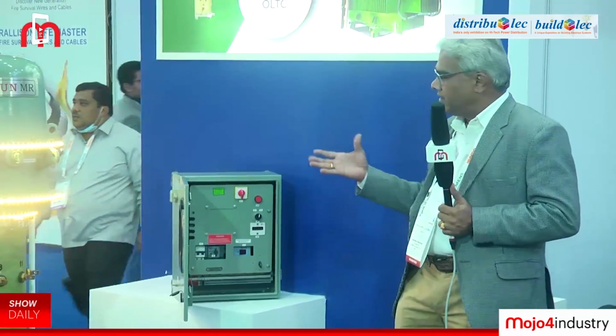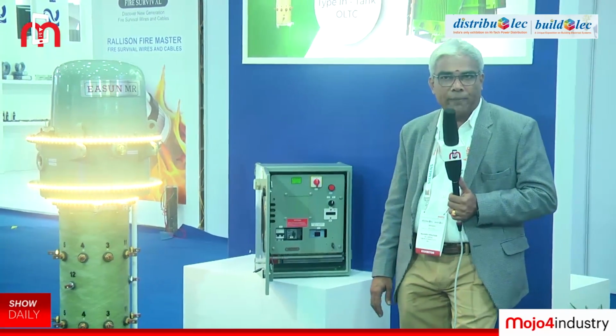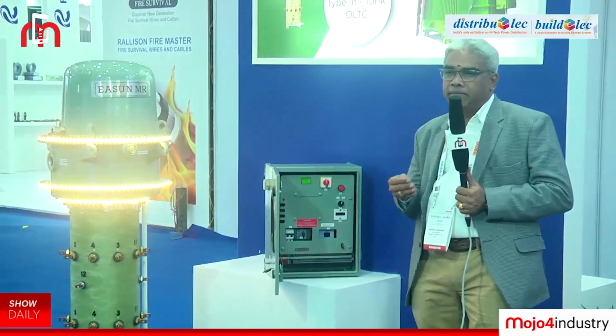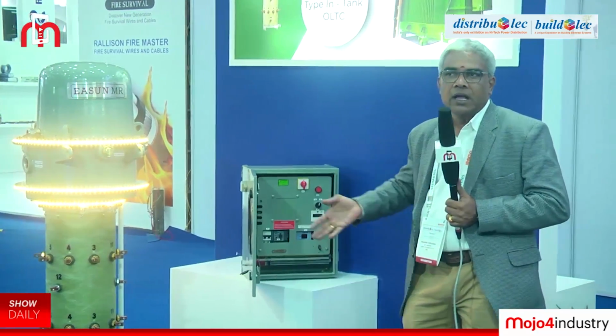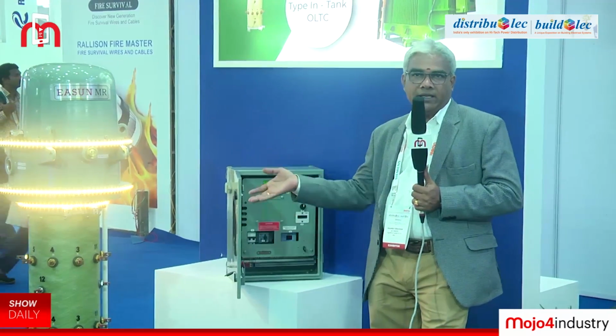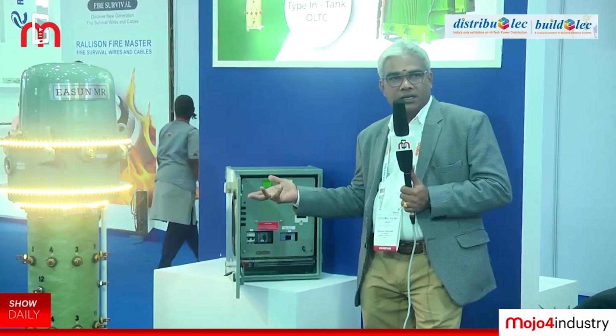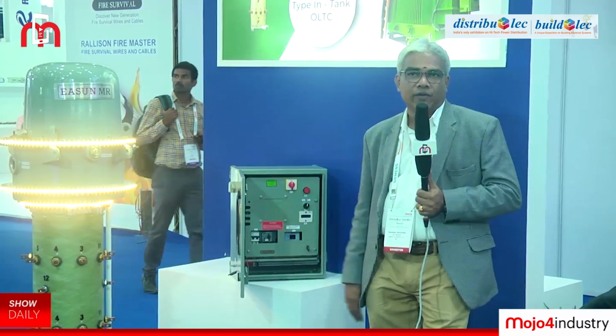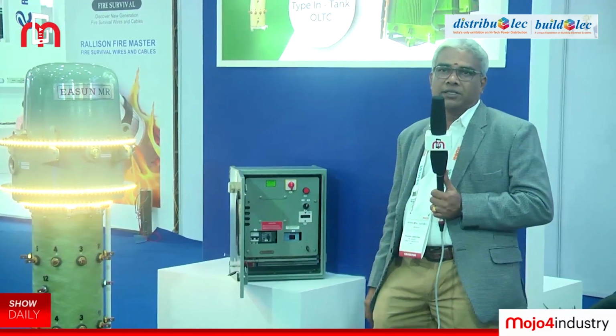This tap changer is very user-friendly, designed for 5 lakh operations. The maintenance duration is once every 50,000 operations, where we change the oil and maintain the OLTC, giving it a minimum life of 5 lakh operations.